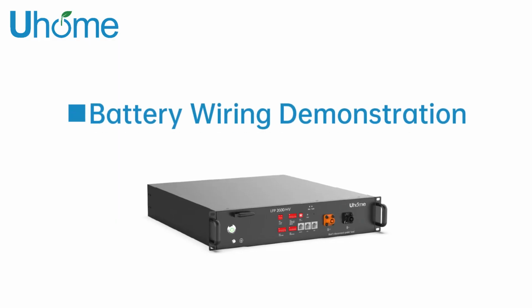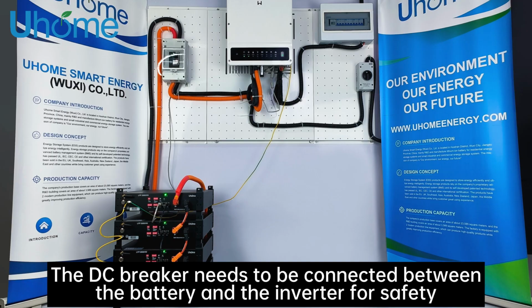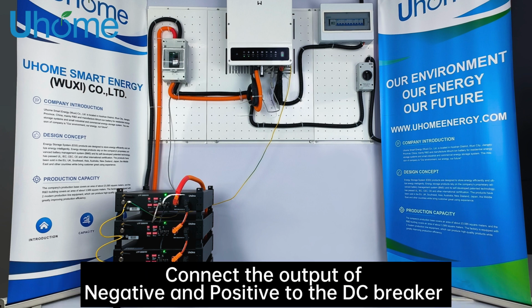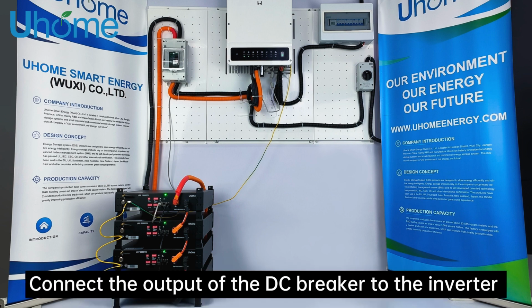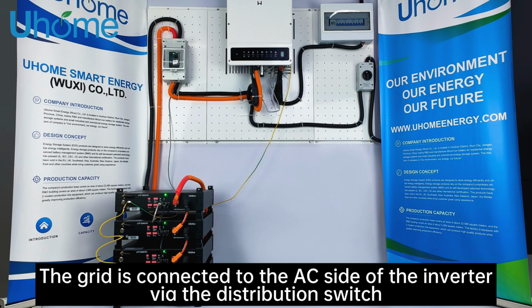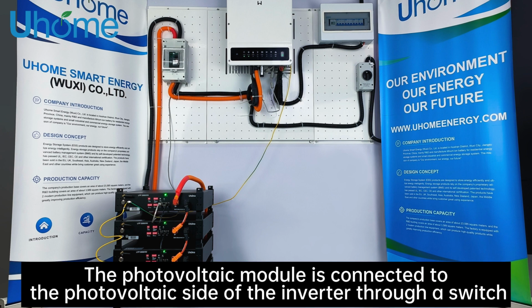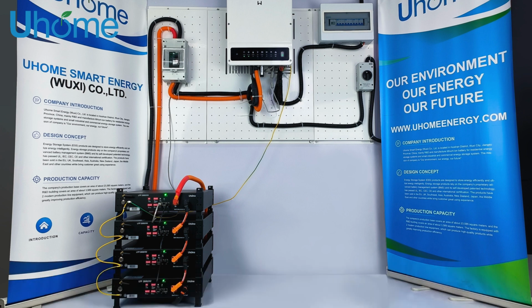Battery wiring demonstration. The DC breaker needs to be connected between the battery and the inverter for safety. Connect the negative and positive outputs to the DC breaker. Connect the output of the DC breaker to the inverter. The grid is connected to the AC side of the inverter via the distribution switch. The photovoltaic module is connected to the photovoltaic side of the inverter through a switch.